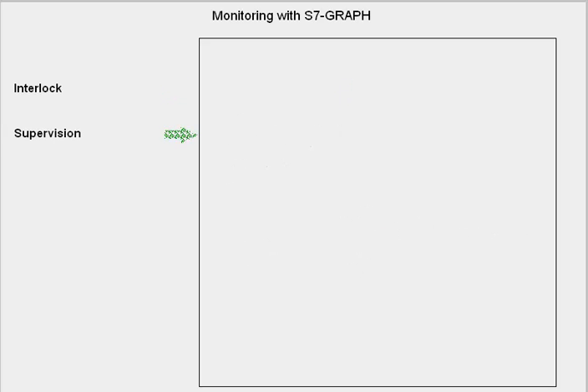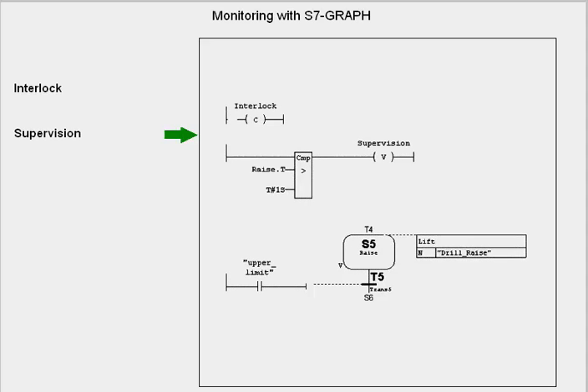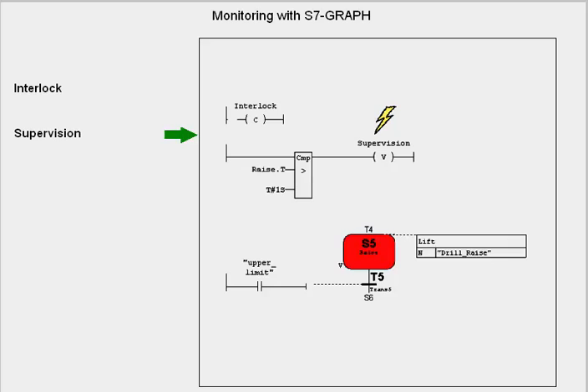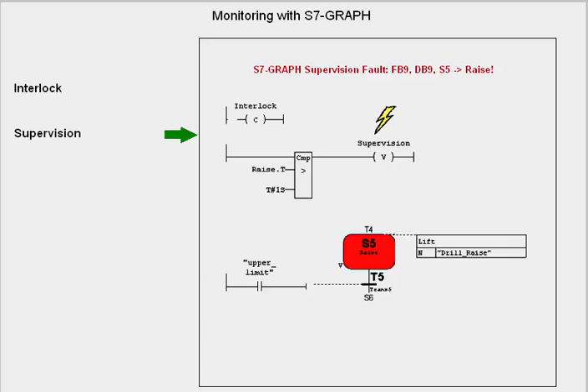Supervision permits you to monitor the step enabling condition in the next step. If the supervision condition is fulfilled, for example through a time monitoring step, a supervision fault is announced, and depending on the settings, the sequencer is blocked. The error texts in both types are generated automatically with specification of the faulty step.